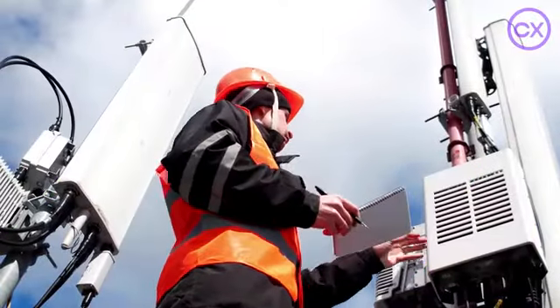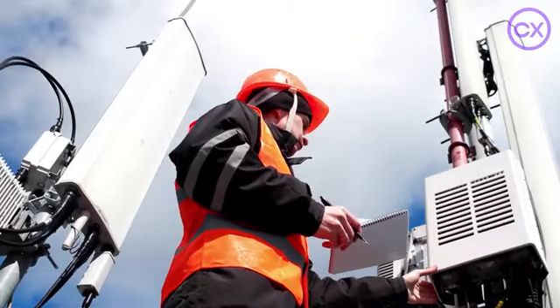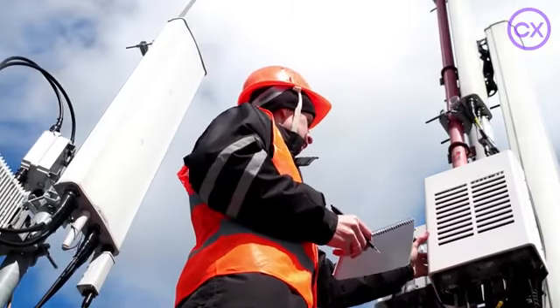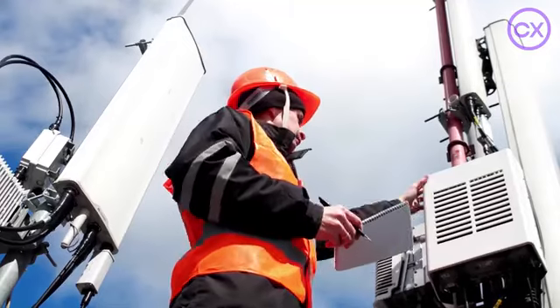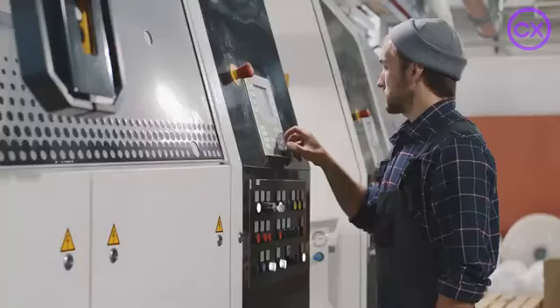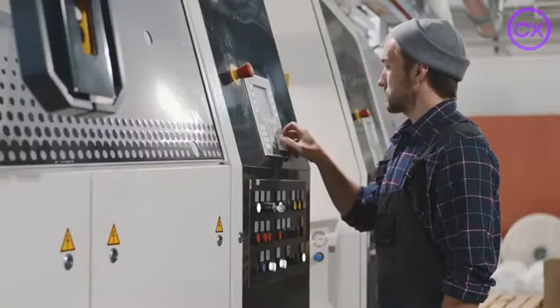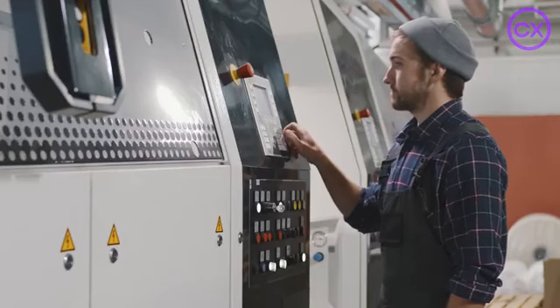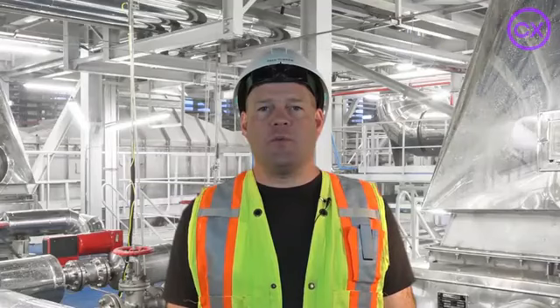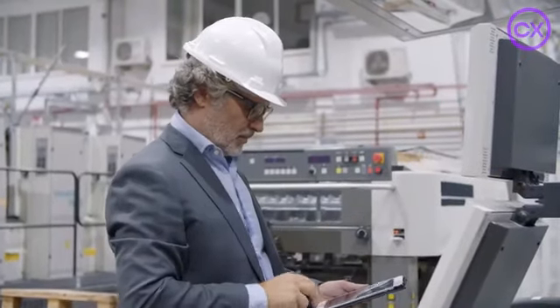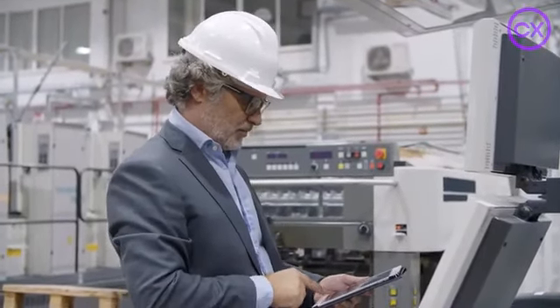Since equipment was verified during factory acceptance testing, it was disassembled and shipped to site, and there is always a possibility of damage during shipping or installation. Pre-commissioning testing confirms that no damage to equipment occurred and that on-site test results align with the test results from the factory. There are a few terms related to off-site and on-site testing.